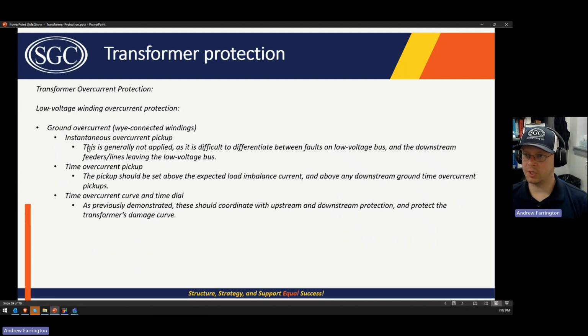For Y-connected windings, again, don't apply an instantaneous overcurrent element, and the time overcurrent is ground protection for a Y winding connection. You want the pickup to be above expected load. So if the system's fairly balanced for that transformer, say it's a 115 kV low side transformer, maybe it's 5 to 10% of the maximum load current. That's a pretty high imbalance. If you set it above that, you're going to be secure.